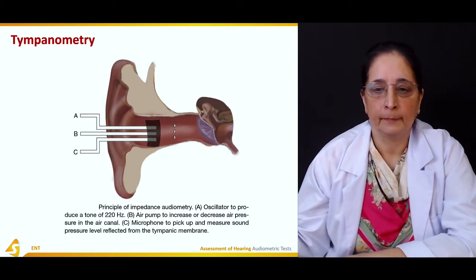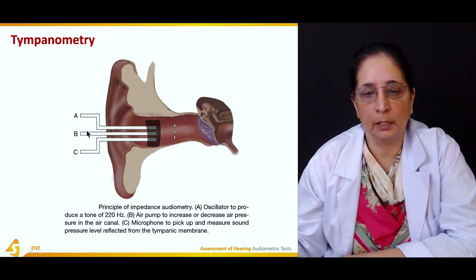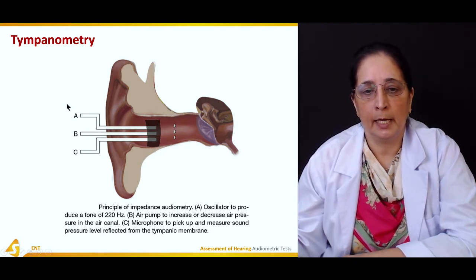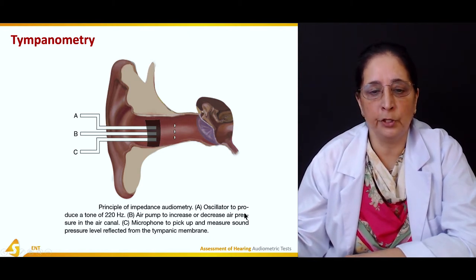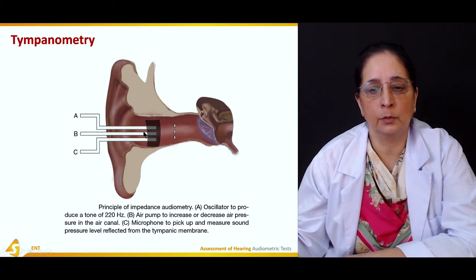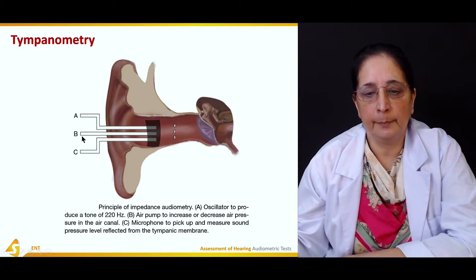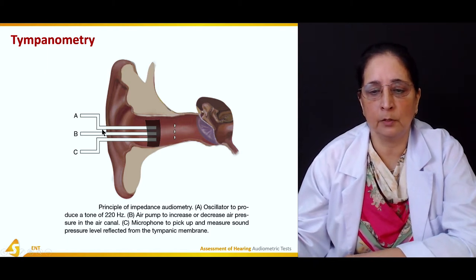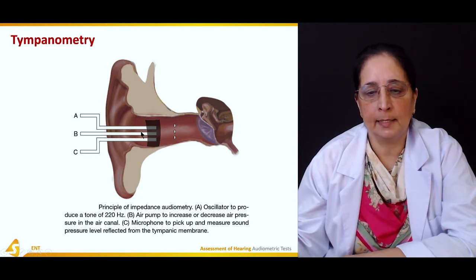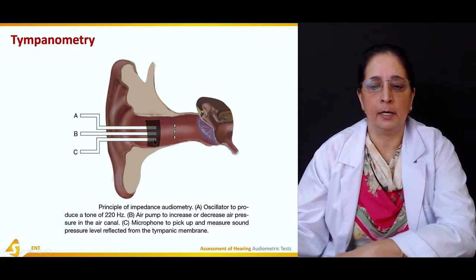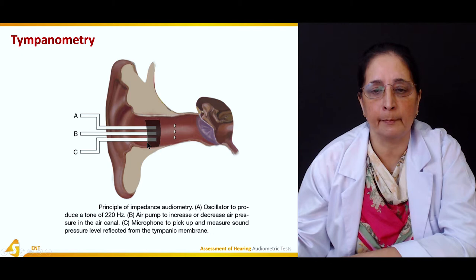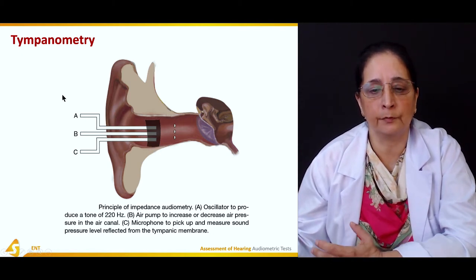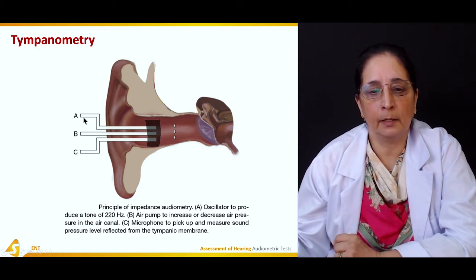In tympanometry, three probe components are used: A is an oscillator to produce a tone of 220 Hz; B is an air pump to increase or decrease pressure in the ear canal; and C is a microphone to pick up and measure the sound pressure level reflected by the tympanic membrane.